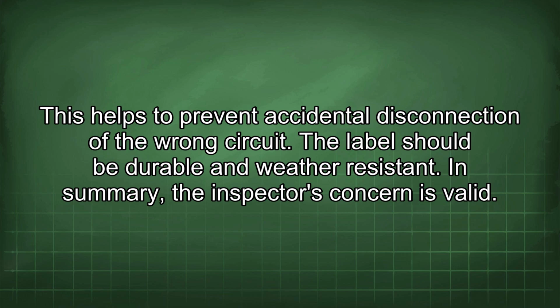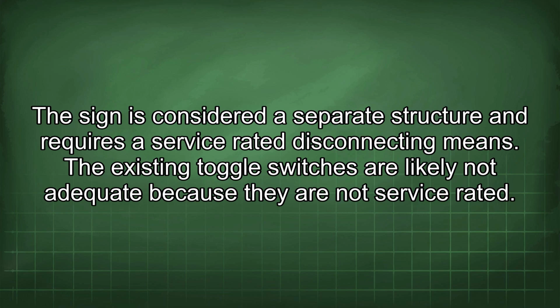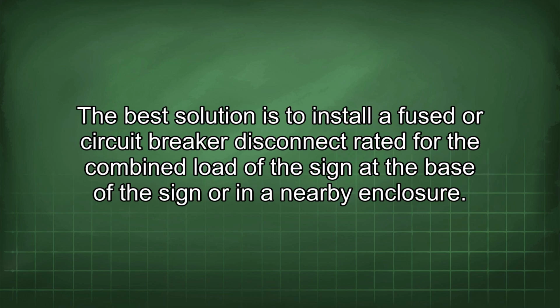In summary, the inspector's concern is valid. The sign is considered a separate structure and requires a service-rated disconnecting means. The existing toggle switches are likely not adequate because they are not service-rated. The best solution is to install a fused or circuit breaker disconnect rated for the combined load of the sign at the base of the sign or in a nearby enclosure.